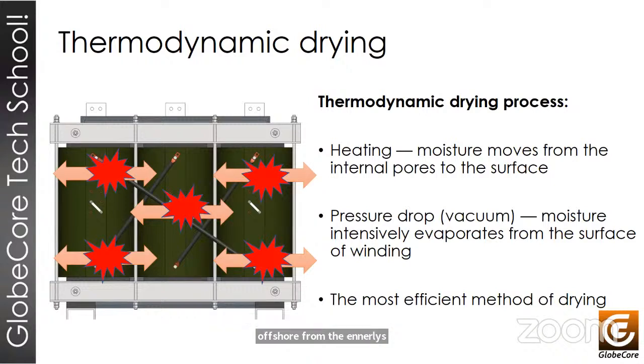A thermodynamic drying process is used to remove moisture from the insulation. The thermodynamic drying process is based on using the phenomena of moisture conductivity and diffusion of vapor from the heated surface of the insulation. The drying process comprises the following stages: convection, heating of the insulation, movement of moisture from the inner layers of the insulation to the outside, and vapor formation and vapor diffusion from the surface of the insulation into the surrounding space.